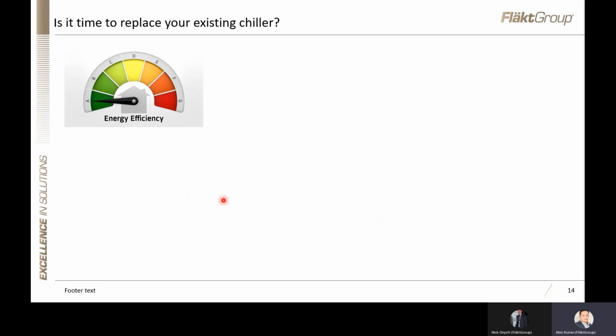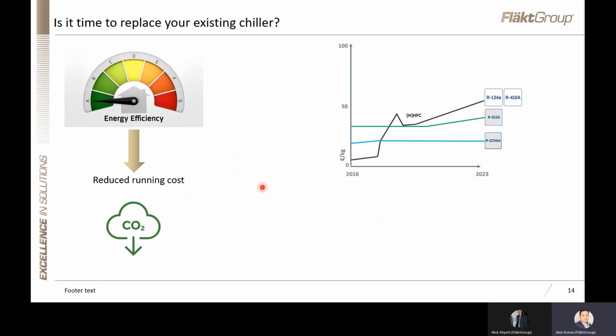Now, is it time to replace your existing chiller, or what factors need to be considered? The first factor is energy efficiency. The new generation chillers are more efficient than the old ones, which saves a lot in running cost and also reduces the carbon footprint. The second factor you need to consider is refrigerant price increase. The graph is an indicative sketch and it's hard to predict the actual price increase. You might notice that R410A and R134A prices have gone up sharply compared to R513A, which has only a moderate price increase. R1234ZD, with its low GWP, looks stable.